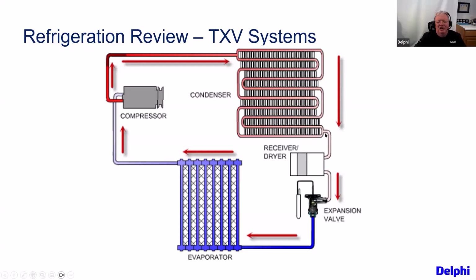When it comes out the other end, it should be a liquid. It'll still be high pressure until it hits the expansion valve, which is a restriction. That restriction causes it to go into a low pressure state, which means it gets cold. The thermostatic bulb with oil in it responds, changing the diaphragm to open and close. So this is a dynamic valve that changes, the expansion valve.